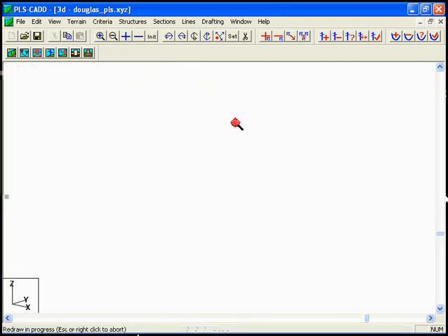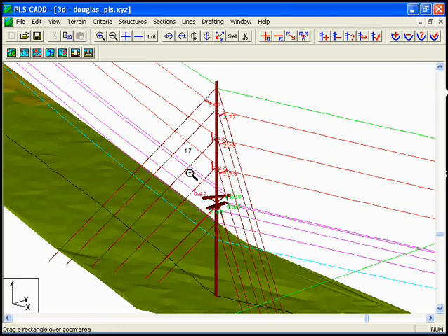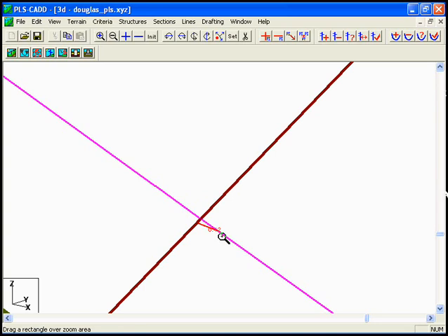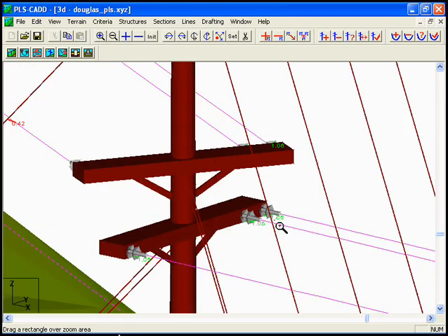In the case of our transmission strain insulators, even though our insulators are 4 foot long, we're only getting a 2.77 feet clearance between the energized end of the insulator and the down guy from the ahead span. An even worse case is in our distribution underbuild, where in this particular case we have 0.42 feet of clearance between our distribution wire and our ahead guy on our lowest phase of our transmission. We do have some other clearances indicated in green for our distribution, but those are where the clearances are acceptable.